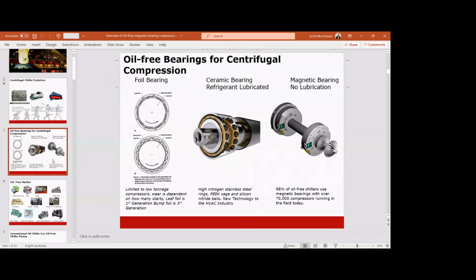The next type of oil-free application is a ceramic bearing. And the ceramic bearing uses liquid refrigerant, which is pumped onto the bearings to keep the bearings cool. There are also limitations on these bearings because of the liquid being pumped onto the bearings and the heat generated by the bearings, we can only use relatively low speed machines or low speed applications on these types of bearings. And so in today's market, they are only used on negative pressure machines, or R1233 machines.